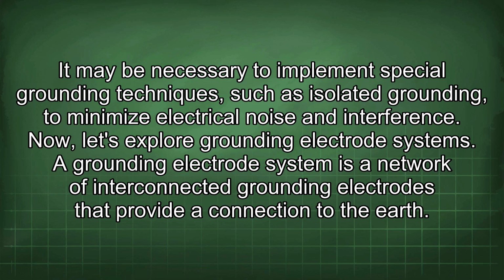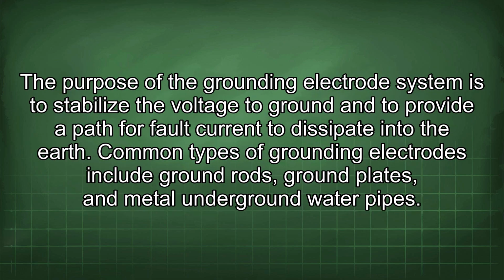Now let's explore grounding electrode systems. A grounding electrode system is a network of interconnected grounding electrodes that provide a connection to the earth. The purpose of the grounding electrode system is to stabilize the voltage to ground and to provide a path for fault current to dissipate into the earth. Common types of grounding electrodes include ground rods, ground plates, and metal underground water pipes.